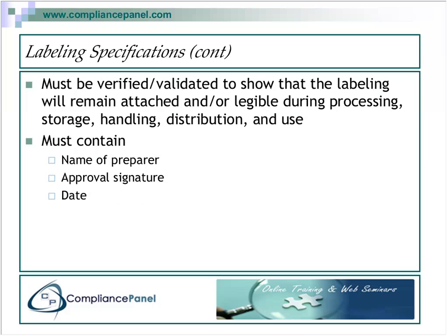Your labeling has to be verified or validated to show that it's going to stay attached. Now this is a no-brainer if you print directly onto your pouch or if you etch onto your instrument, but in many cases that's not done. In many cases it's done by adhesion. And in these cases you have to show in advance, as part of a verification and validation, that your labeling is going to remain attached and legible during all its normal processing, handling, distribution, etc. And your labeling specifications must have who prepared the label, it must have an approval signature that somebody has inspected the labeling, and it must have the date that approval was done.